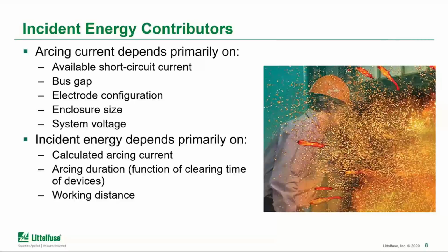So we look at the arcing current. The available fault current is a major parameter in that discussion. So that's the current that can be produced by the transformer or generator. And the second point there is the bus gap, so the air gap between the phase conductors where the arc is occurring.